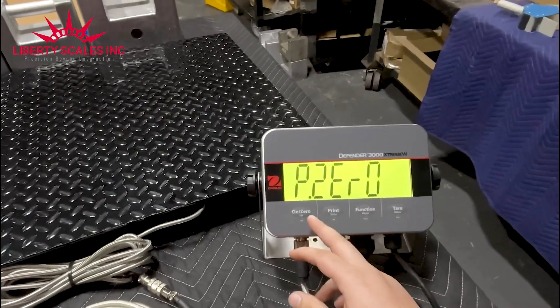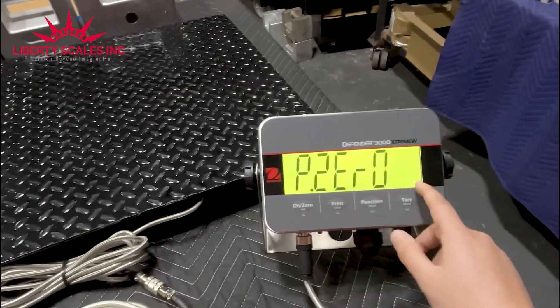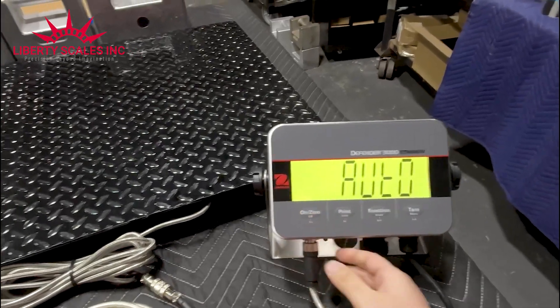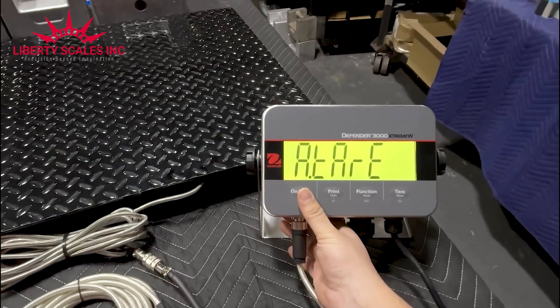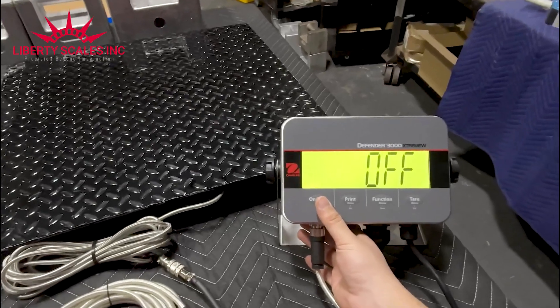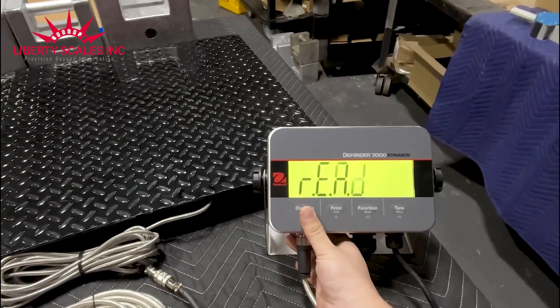Next is power-on zero — I enter it and select on, which is good. Power on unit I leave on auto so it starts at whatever unit you last used. Auto tare I set to off — we don't want it to automatically tare an object. I press yes and it says end; press yes again and it goes back to the main menu.